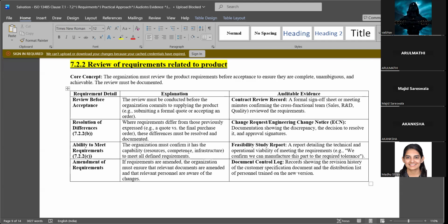When you do an understanding also, it's not that he is my friend, we have a common understanding. That's a different thing. Though he is a friend, now it's mandatory as per the regulations that you should have it, even with outsourced activities like suppliers, contract manufacturers, or outsourced sterilization units, whatever you outsource. You should have a legal binding, in the sense that it is written, documented, and signed by the top management of both parties, so that if some mischief happens, it could be on either side. That guy may cheat or we may cheat them. Since it is legally binding, they can go to the court. It becomes a legal issue. Those are the amendments.